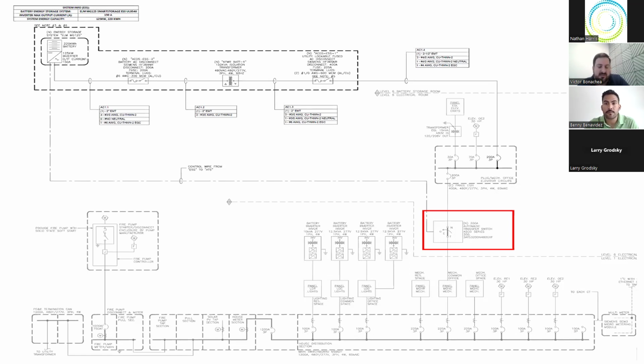switch. So in this sequence, if utility power fails, and immediately upon utility power failing, the inverter is shut off because they're still technically tied to utility, there's no longer any power on this system for that transfer switch to flip its contacts and island that elevator distribution board and that inverter, which would allow you to turn on that inverter. When it's a generator application, that's not a problem because on that emergency side of the switch, the emergency would start up, the generator would start, and then we would pull power from the emergency bus to energize those solenoids or motors to drive the switch.